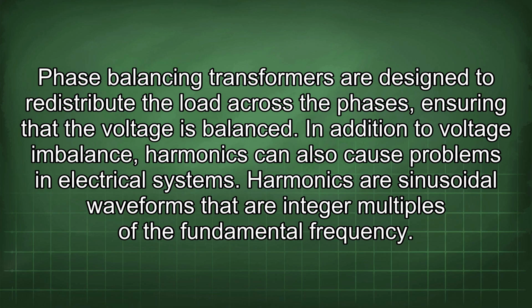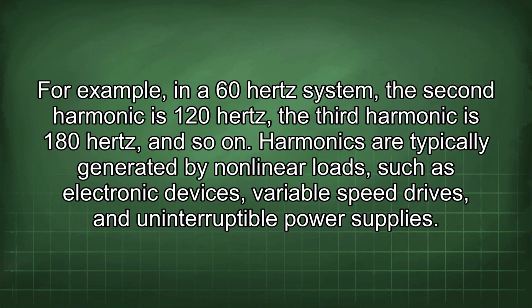Harmonics are sinusoidal waveforms that are integer multiples of the fundamental frequency. For example, in a 60 Hz system, the second harmonic is 120 Hz, the third harmonic is 180 Hz, and so on. Harmonics are typically generated by nonlinear loads such as electronic devices, variable speed drives, and uninterruptible power supplies.